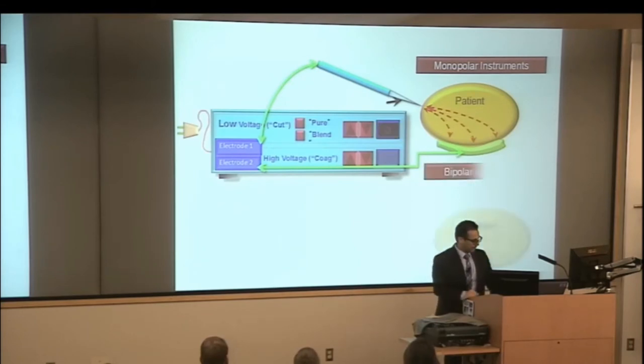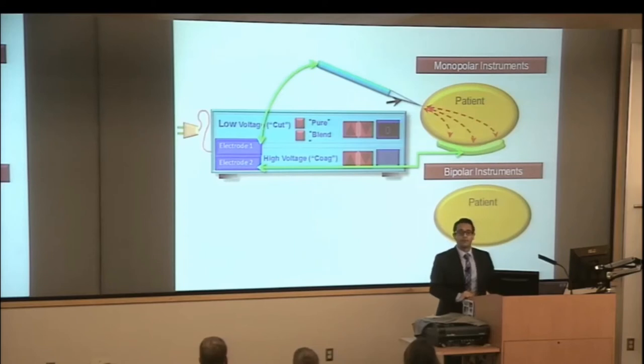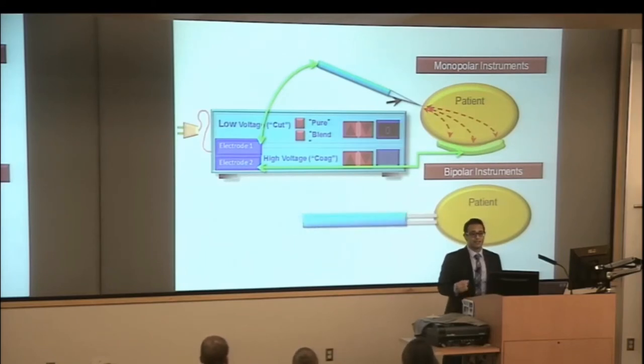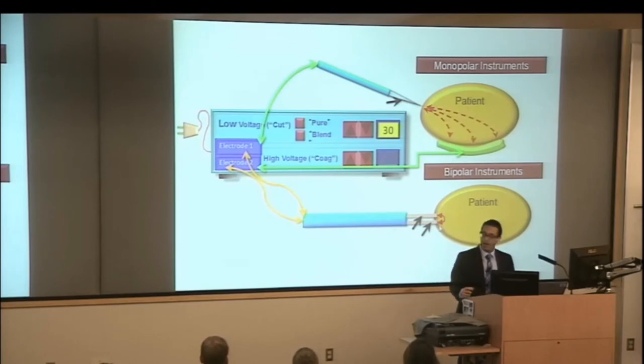Now contrast this to bipolar instruments. You have, again, two electrodes, but the difference here is the two electrodes are in the device itself. When you activate that, the current is limited to this path right here. So you can see how bipolar instruments can be a lot safer, because you don't actually have current going through the body of the patient to other places - it's restricted to this area.